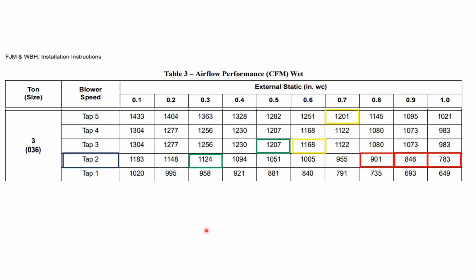So let's say I set my static pressure and I test it, and I'm way up here in the 0.9 number, all right, and I'm on speed tap 2, I'm only putting out 846. Well, I have to have 1115. So you can see I'm about 300, roughly almost, CFM shy.